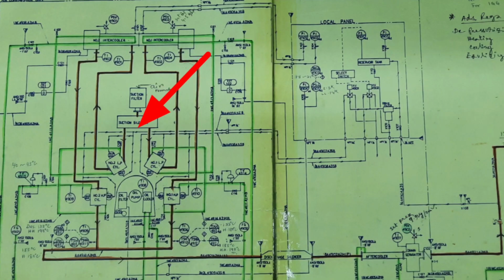So I am explaining again from the suction filter. The air comes to the suction silencer and is divided two ways. One is the number 1 LP cylinder, another is the number 2 LP cylinder. From the number 1 cylinder it will go to the number 1 intercooler. From the number 2 cylinder it will go to the number 2 intercooler. From the intercooler this air will come out and go to the number 1 HP cylinder. First one is LP, second one is HP cylinder, and again from number 2 it will go to the number 2 HP cylinder. From this intercooler it comes out, and finally it will discharge.